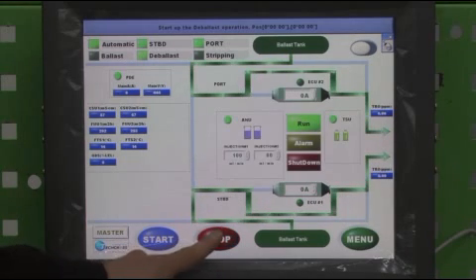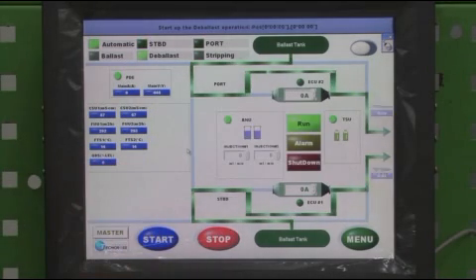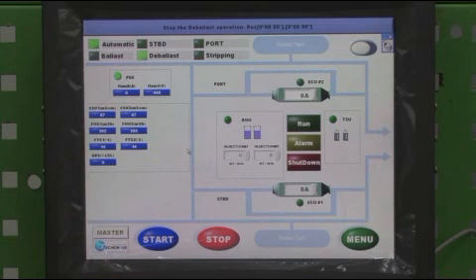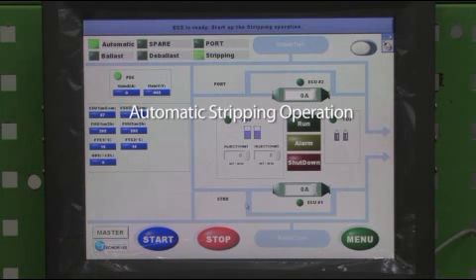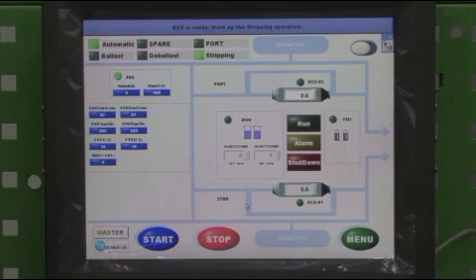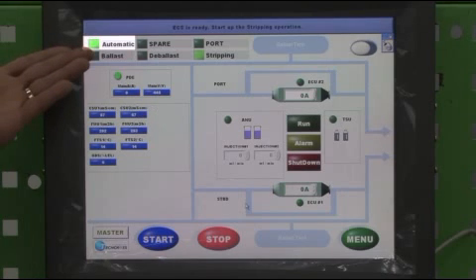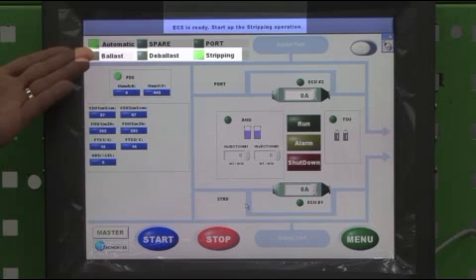Step 5. Stop the ballast pump first to stop the deballasting operation. Click the Stop button on the HMI screen to stop ECS operation. 5. Automatic stripping operation. Step 1. Make sure that automatic is on. If manual is on, press to change to automatic. Step 2. Select operation mode after checking related pumps and valves. Please refer to checkpoints before operation.